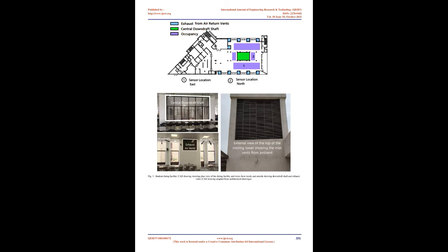Upon subsequent installation of the cross baffles, the temperatures for the two floors in the student dining hall show a much closer match, as seen in data recorded using the same instruments and similar arrangement in April 2018 in Fig 6, time plots and box plots. 6. Discussion. On the whole, passive cooling systems prove to be effective and meeting expectations when the ambient conditions are hot and dry, typically 3 months in a year.